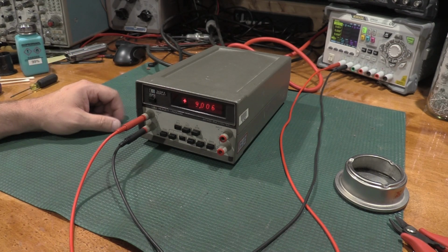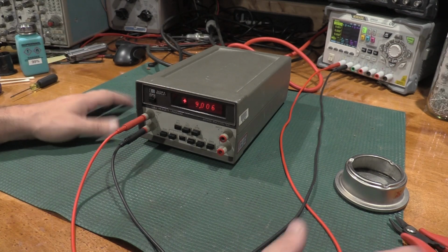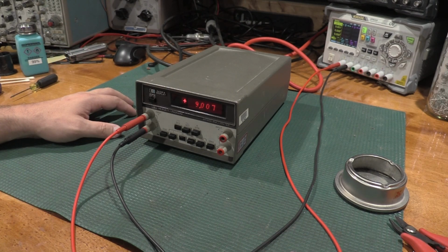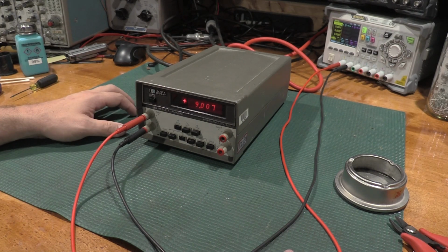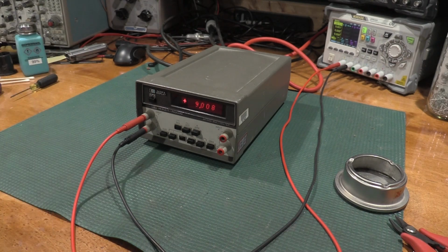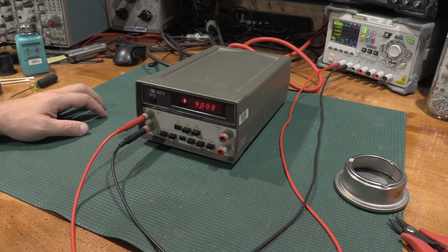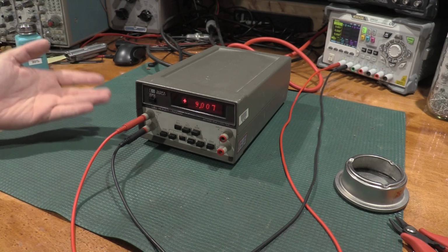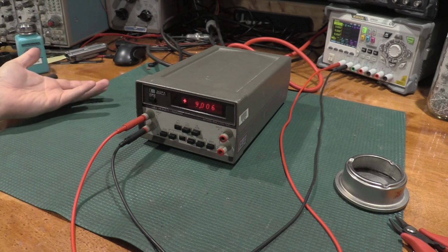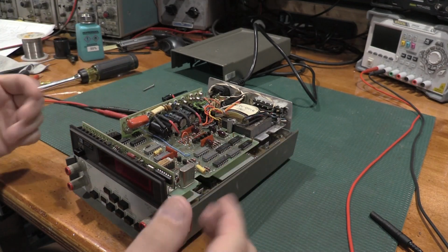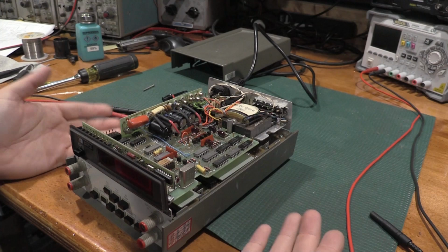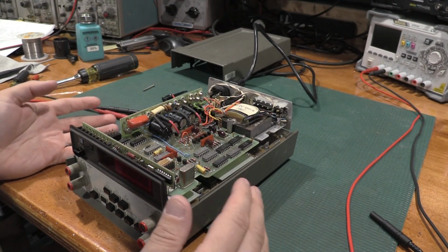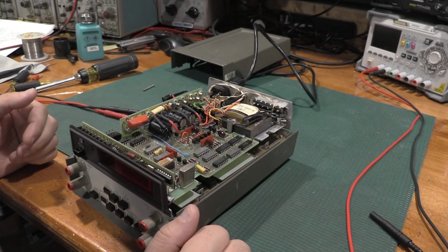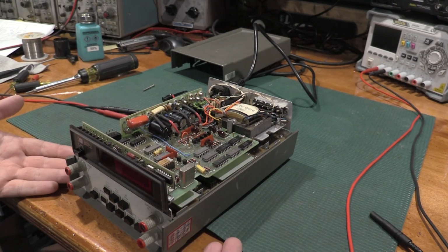Then we've got to warm up the cal gear. Not going to warm up the cal gear tonight, just for the length of time it takes to warm that gear up. It's a minimum of an hour and a half warm-up time for the 7.5 digit meter, the AC and the DC ranges. So we're going to let it run. And then once we do the alignment, we'll talk about what this is replacing. Taking a look at the service manual for the display unit, because we have two separate meters, we need to do two separate alignments.